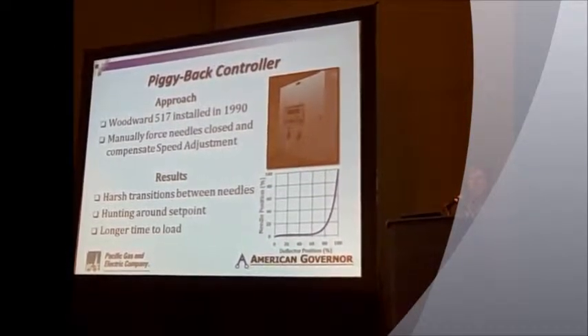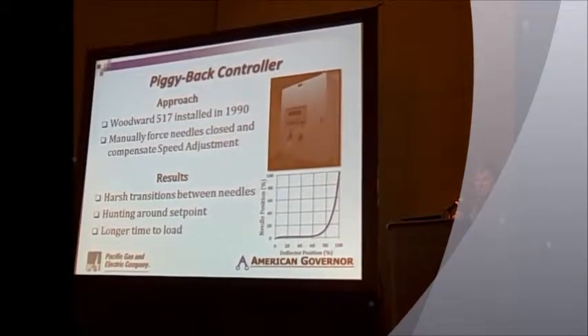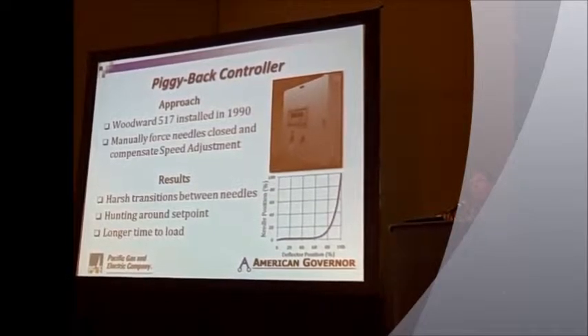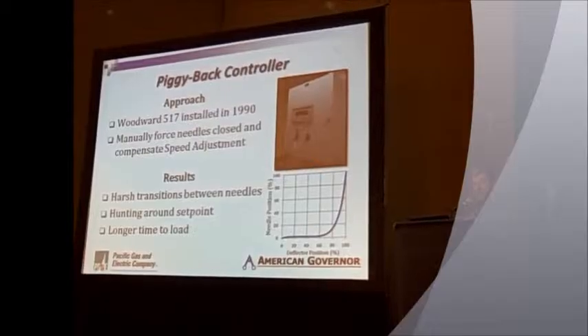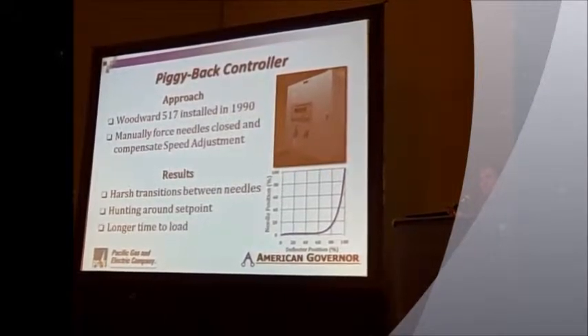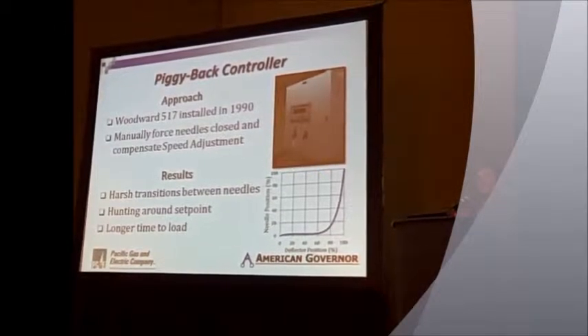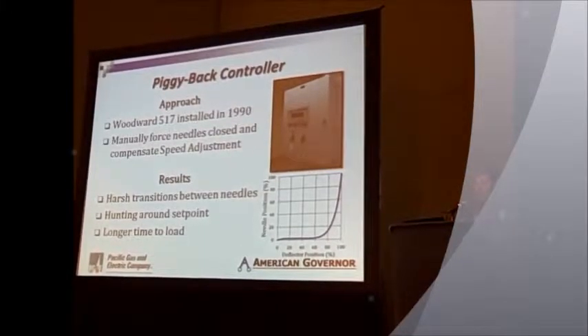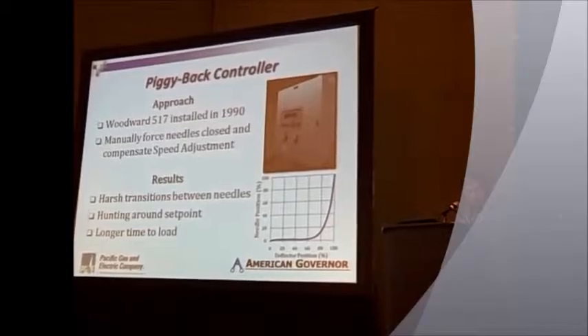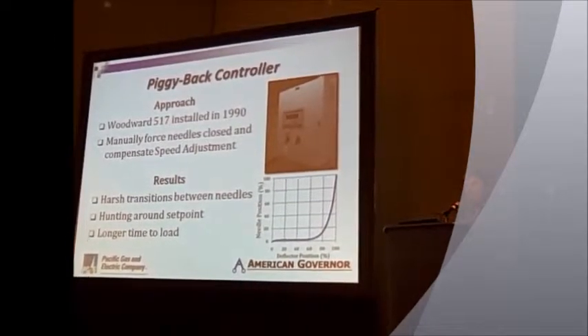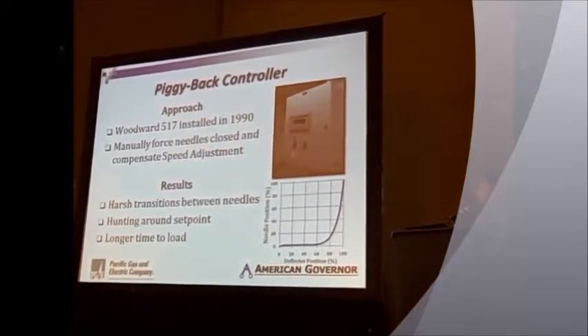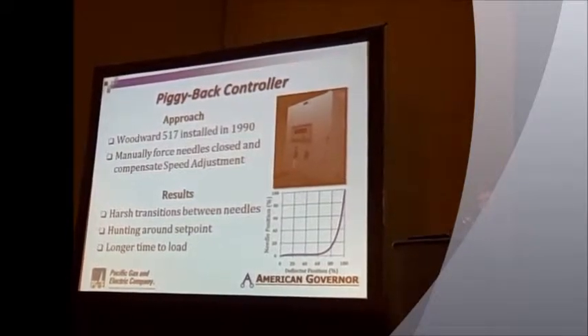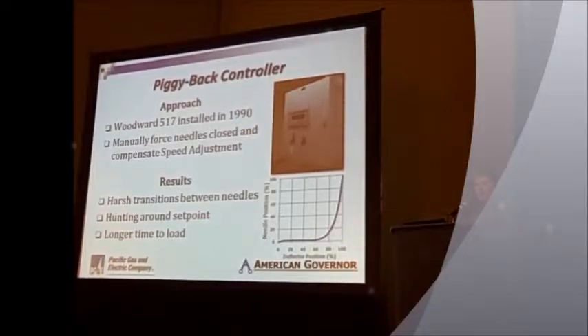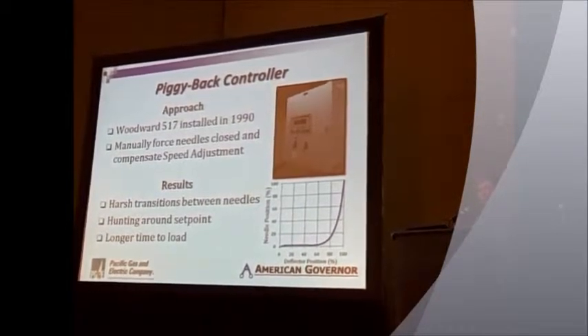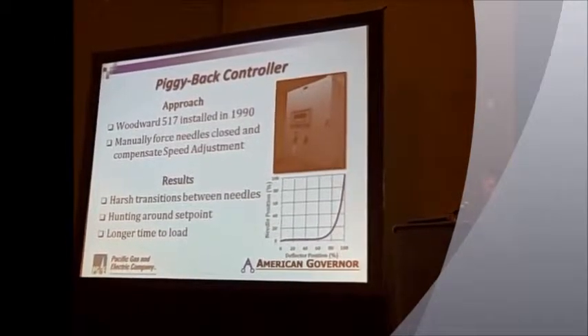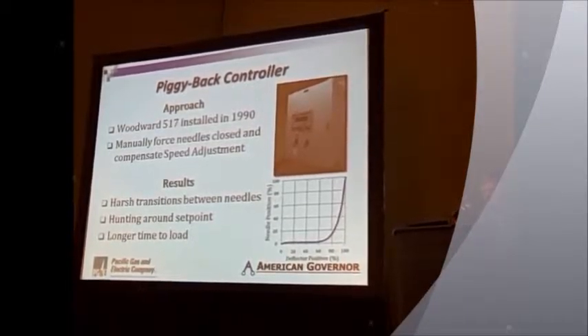In addition to that, when we controlled the megawatt set point, we were pulsing the speed adjust motor so that it never really knew where we were trying to go. It was just kept pulsing up until it got there. So we didn't have the ability to tell it how many needles it needed to have to get to that particular location. It would have to transition through the whole 2-4-6 instead of just going directly, starting to open all 6 needles. And the last item was that because of all the cable restoring and all the weights, there was always a lot of slop in the system, so the speed adjust set point would never match the ISO set point. And so there was a constant battle. It was always in a hunting situation. We fought that for a couple of years and finally abandoned the 517 and the 2-4-6 concept.